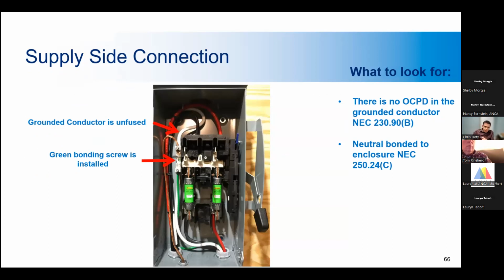So in light of the fact that the supply side conductors are similar to a second set of service entrance conductors, and that they are unprotected from supply or utility side current potentials, the disconnect that serves the supply side connection must be bonded similarly to a service panel. In service panels, the neutral and the ground are bonded together and to the enclosure. You can see here the ground wire is the bare wire, and the neutral wire and the ground wire are bonded to it via this green bonding screw. This allows the overcurrent protection devices to operate properly, and it also grounds the enclosure.